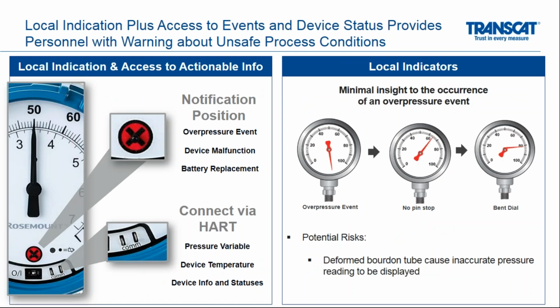The other thing that the wireless pressure gauge can show is to notify you if there's something like an overpressure or a malfunction. There are many Bourdon tube gauges out there today where there's actually two gauges, and if an overpressure event happens, one of those dials drops, and it can tell an operator the next day that at some point in time there was an overpressure. That's what this indicator can do. The same thing, the dial can move to that indicator, and you know that something has happened. And then the beauty of this gauge is that you can connect to it via HART protocol, any sort of HART communicator, and you can see all the pressure variables, the device temperature, any sort of status or indication that something's happened, and you can take action on that.